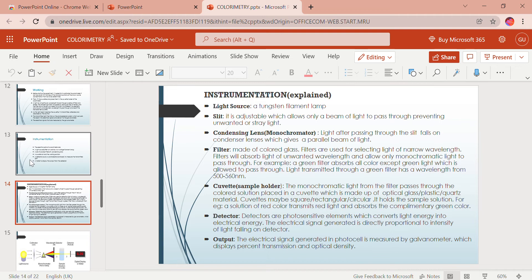For example, a green filter absorbs all colors except green light, which is allowed to pass through. Filters can be absorption filters or interference filters. The monochromator consists of an entrance slit, absorption or interference filter, and then a prism or diffraction grating for wavelength selection, followed by an exit slit. Through the exit slit, light passes to the cuvette. The cuvette holds the sample — monochromatic light from the filter passes through the colored solution placed in a cuvette made of optical glass, plastic, or quartz, with circular, rectangular, or square shape.